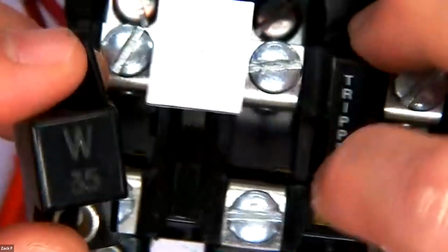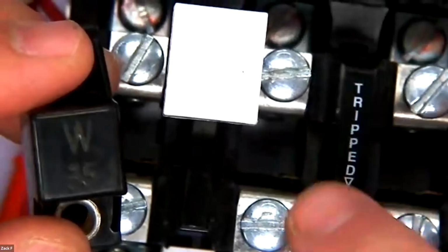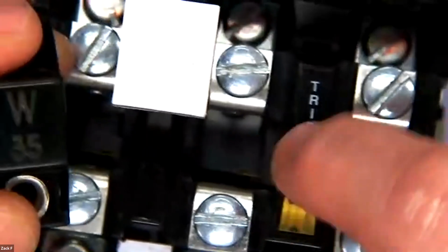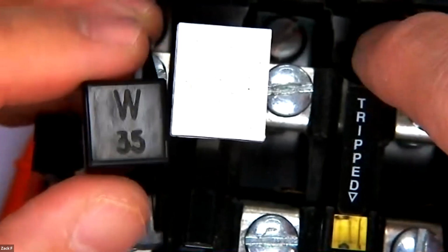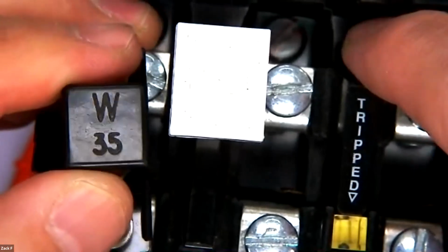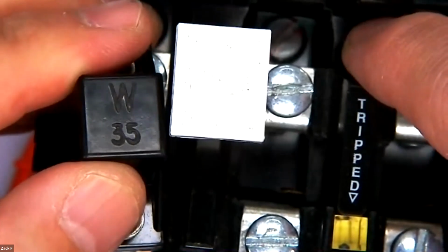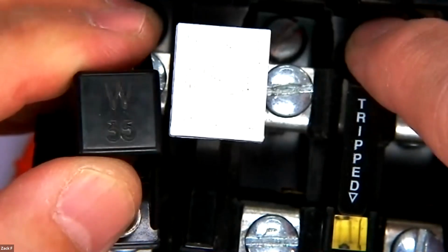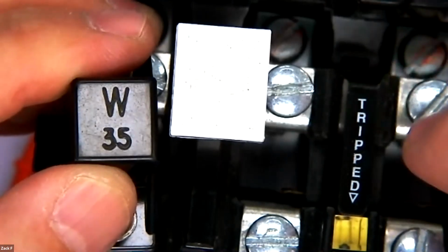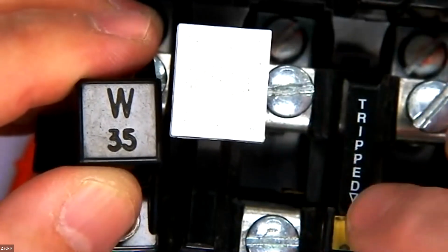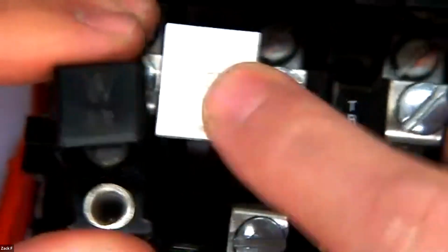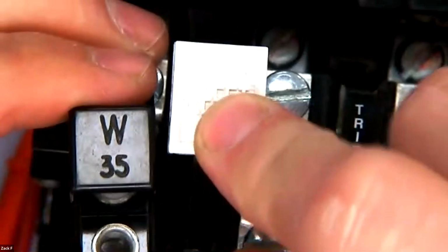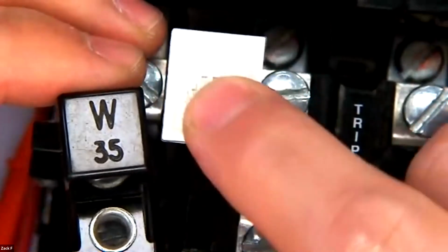And this is a nice NEMA motor starter. It's got a little trip window in there so you can see if it's tripped. If a motor does overheat, whether the bearings are going bad or you put too much load on it for too long and this trips, you might not be able to reset it right away because it's temperature based. It has to cool off before you can reset it. So if you ever see one tripped in the field, you might have to give it some time to cool off before you can reset it.